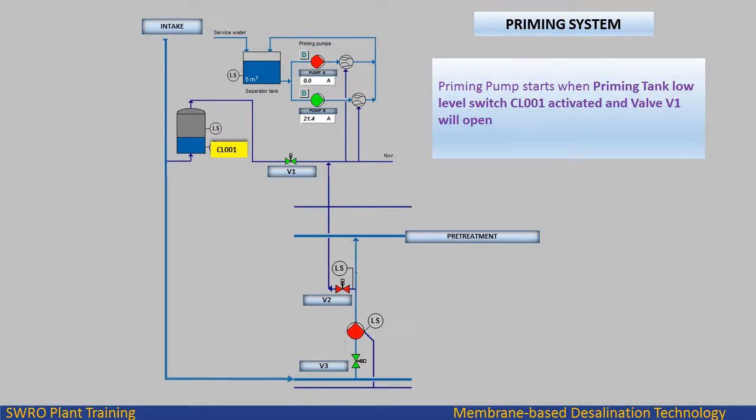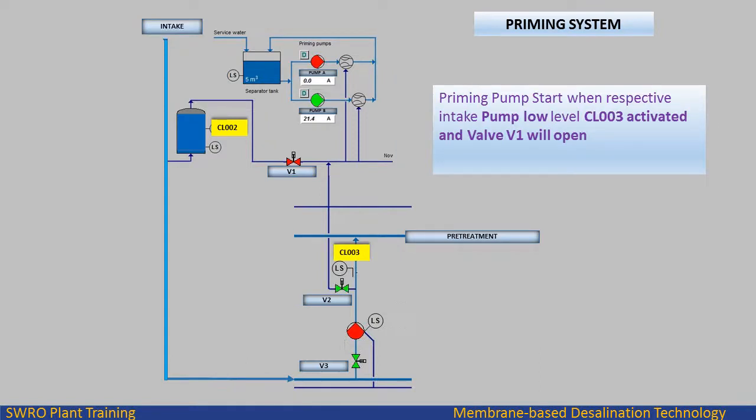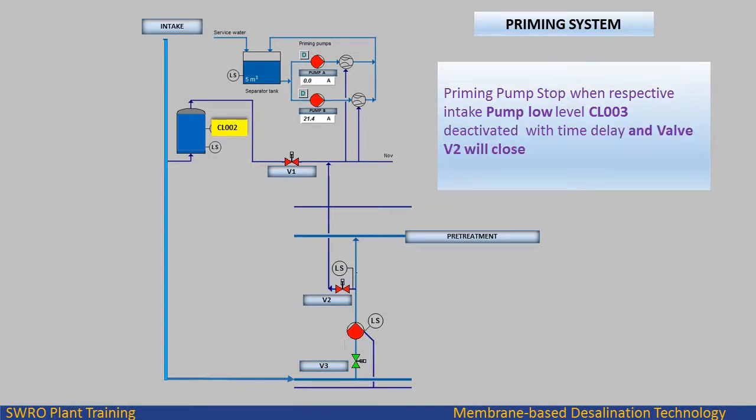Priming pump starts when priming tank low level switch CL001 is activated and valve V1 will open. Priming pump stops when priming tank high level switch CL002 is activated and valve V1 will close. Priming pump starts when respective intake pump low level switch CL003 is activated and valve V1 will open. Priming pump stops when respective intake pump low level is deactivated with time delay and valve V2 will close.